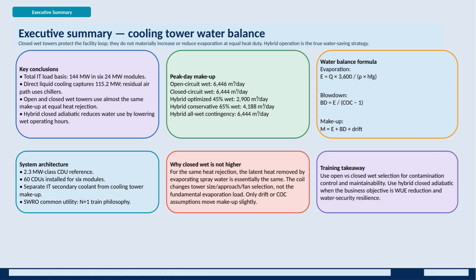Now, why doesn't closed wet cooling show a higher water usage? For a given heat rejection, the latent heat removal through evaporation is essentially constant. The presence of the coil affects tower size, approach temperature, and fan selection, but doesn't fundamentally change the evaporation load. Slight differences in makeup water come from assumptions about drift losses and cycles of concentration.